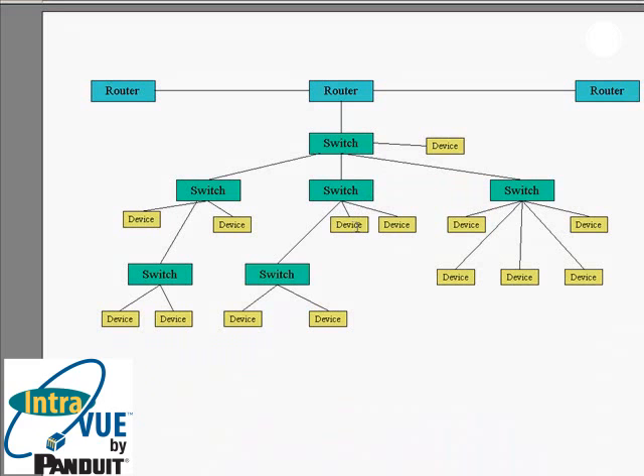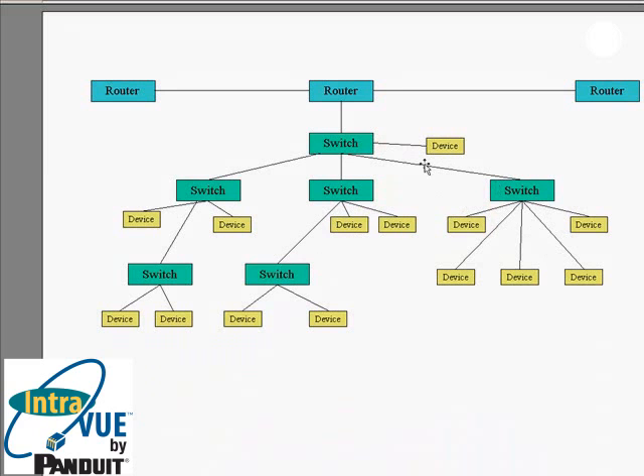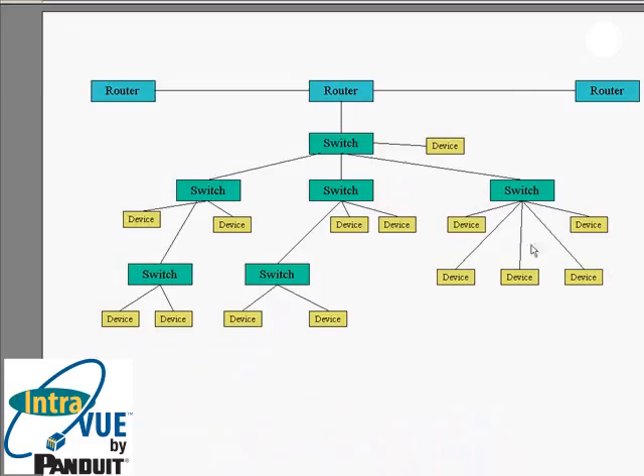IntraVUE should be placed on a switch which is located close to the router, inside the plant network. The statistics collected by IntraVUE will then match the enterprise view of the network. Another example is an operator station which is being fed data by many devices. The main concern in this application is the flow of data to the operator station.